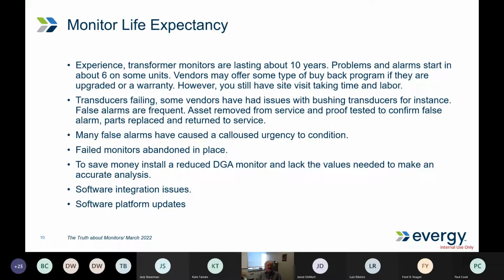So yeah, we waited a while to put that on there because we started seeing some degradation through our yearly testing. And I still think that's a valuable thing to do—go to your substations, pull a yearly sample on the tap changer oil, on the main tank oil, and start to see how it's trending.